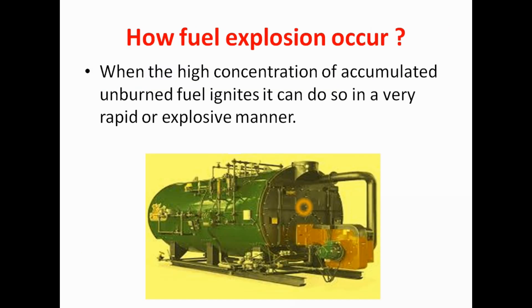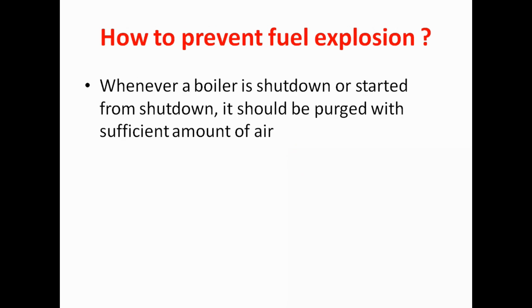Now, how to prevent this? For preventing this, there is a very simple method. Whenever our boiler is shut down or started after a shutdown, it should be purged with a sufficient amount of air. Purging means we stop the flame and only start the blower, so that excess unburned fuel present in the furnace will go out through the chimney, and the fuel-rich environment from the furnace will get removed. This is the method by which we can prevent fuel explosion in the boiler.